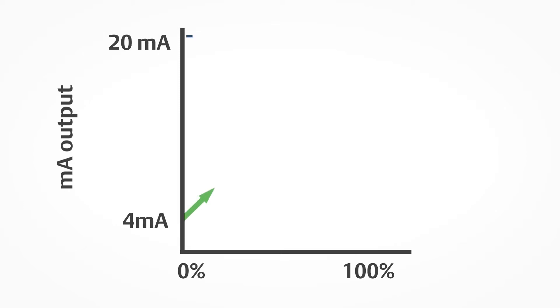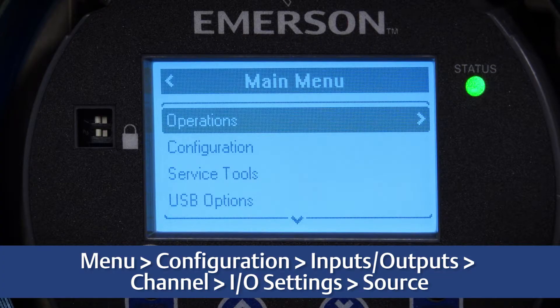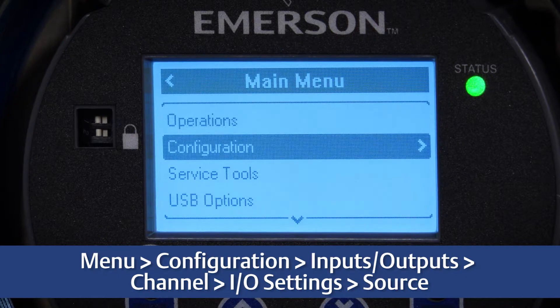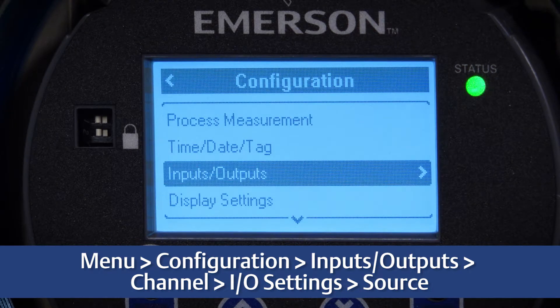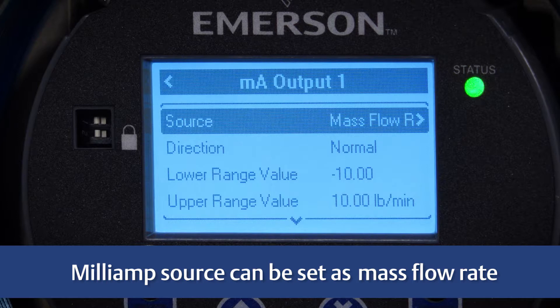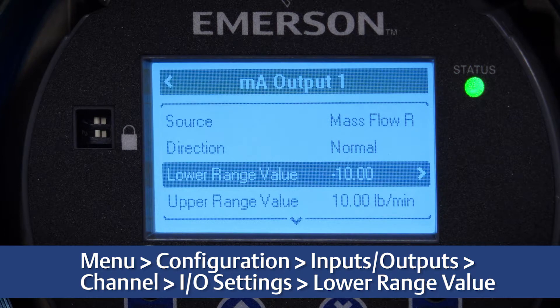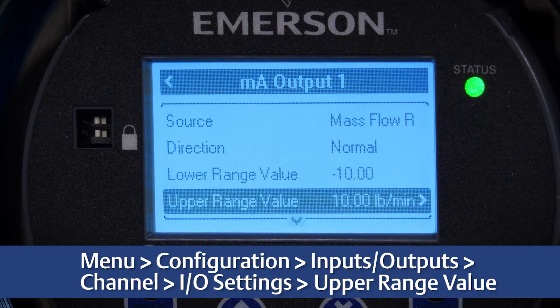The milliamp outputs are used to report current values of process variables. The milliamp signal varies between 4 milliamps and 20 milliamps in proportion to the current value of the assigned process variable. First, configure the milliamp output by using the display and selecting Menu > Configuration > Inputs/Outputs > Channel > IO Settings > Source. For example, the milliamp source can be set as mass flow rate, volume rate, temperature, density, or drive gain. Second, configure the range for the milliamp output by selecting lower range value (4 mA signal) and upper range value (20 mA signal).